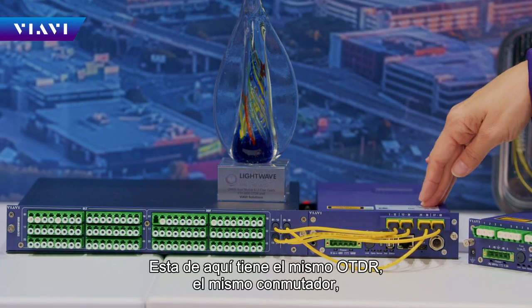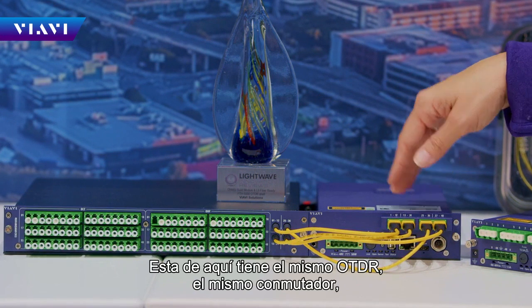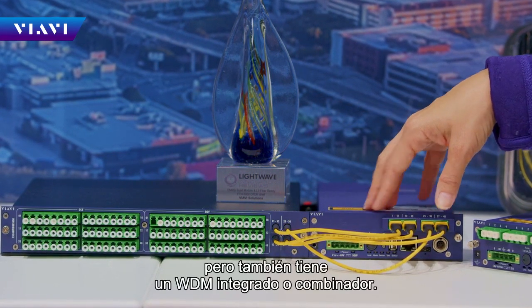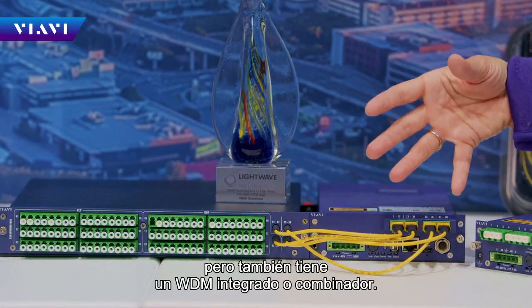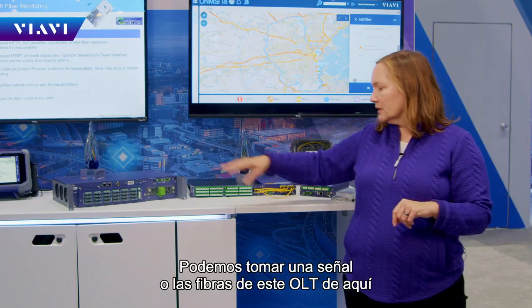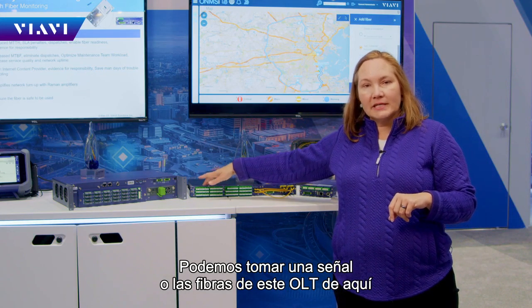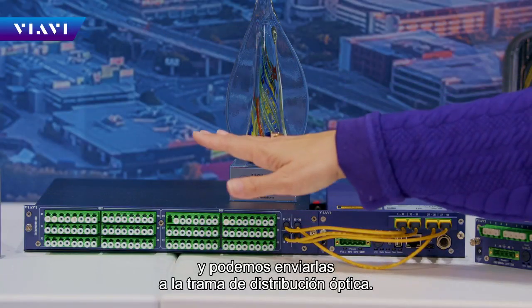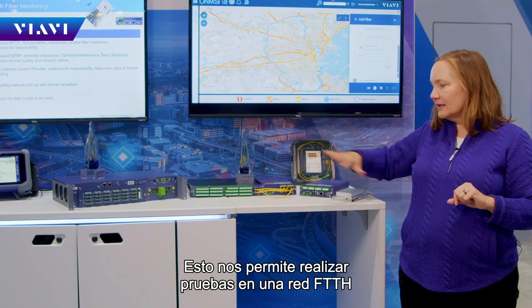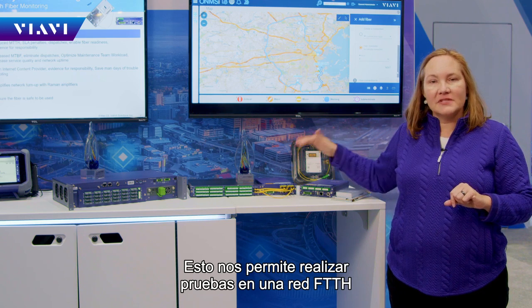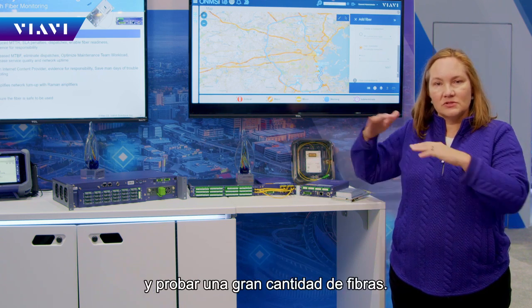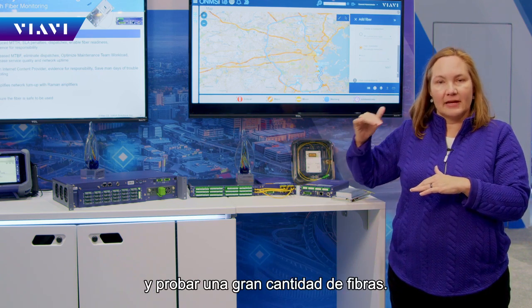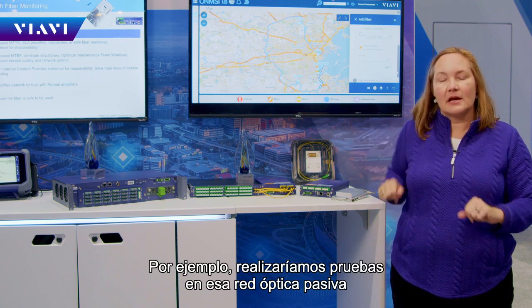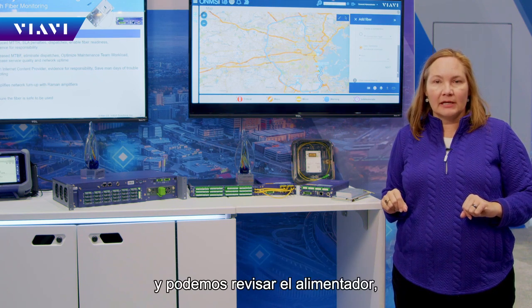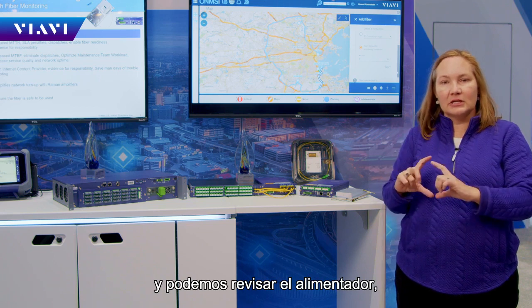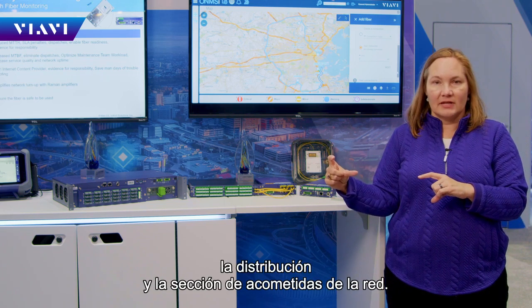So this here has the same OTDR, the same switch, but it also has a built-in WDM or combiner. We can take our fibers in from the OLT here, and we can send them out to the optical distribution frame. That allows us to test a FTTH network and do very high volume fibers. For example, we will be testing down that passive optical network, and we can look at the feeder, the distribution, and the drop section of the network.